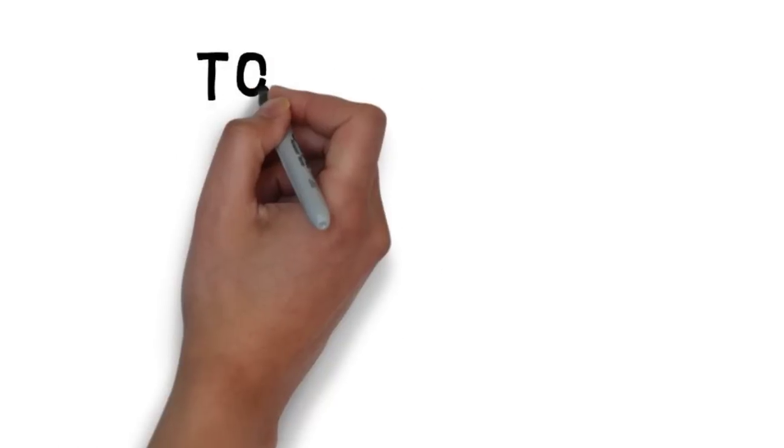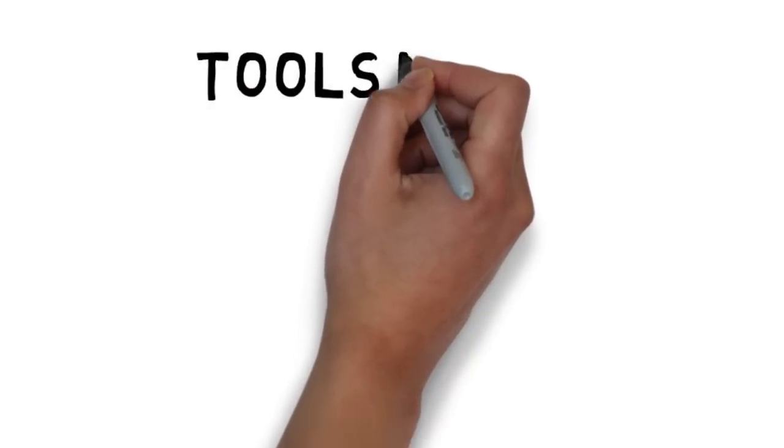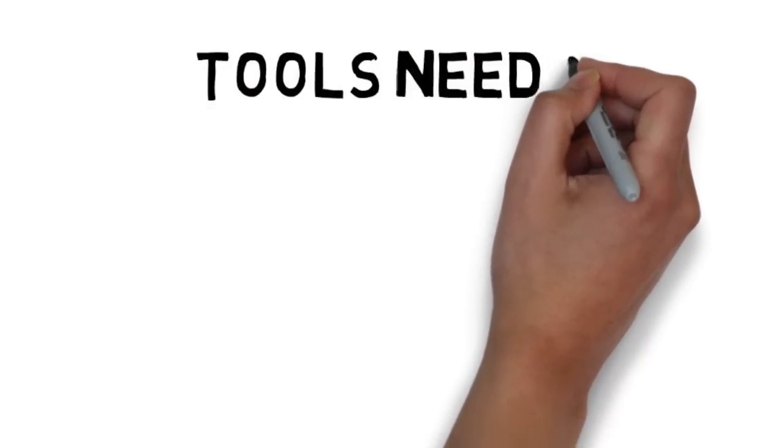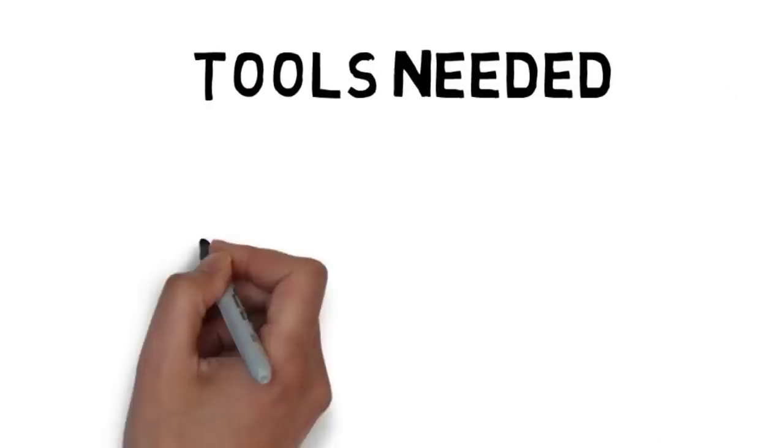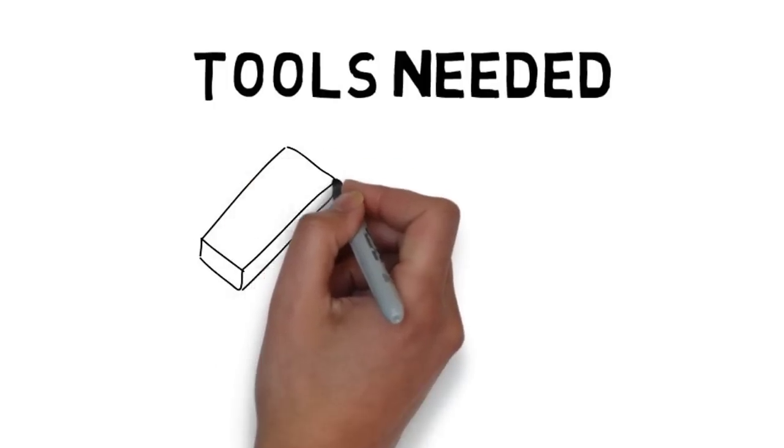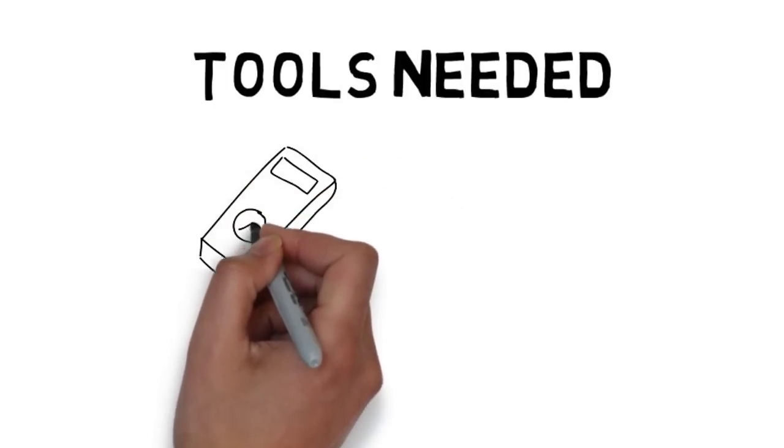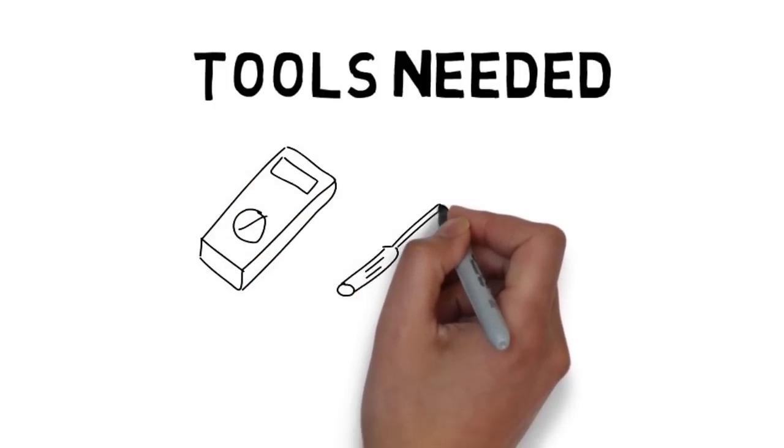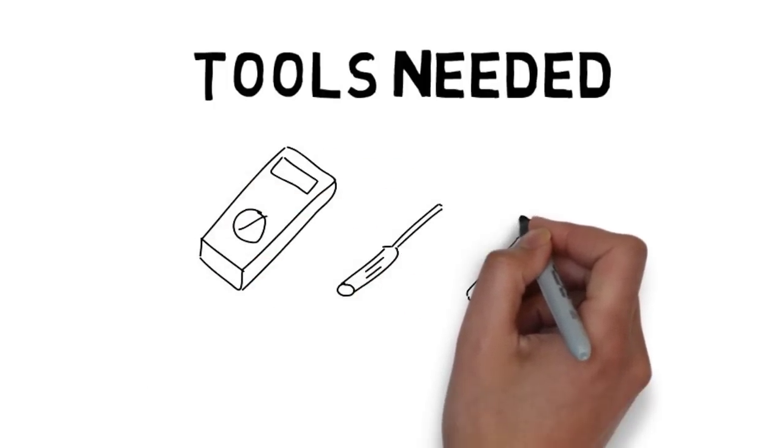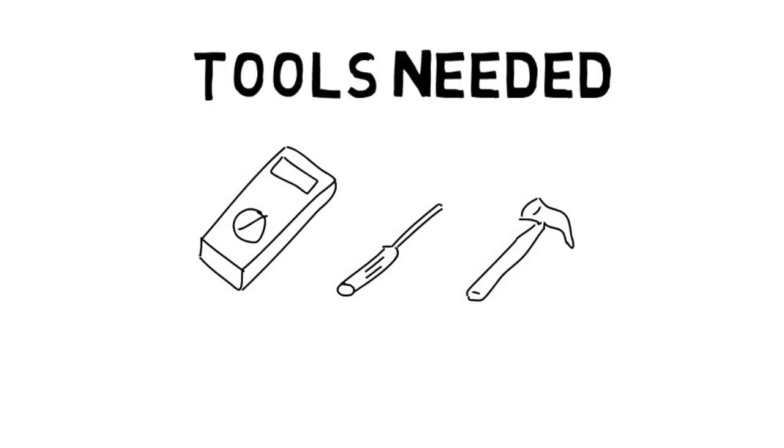You don't need any expensive tools or special tools to troubleshoot a scale system. You will need a multimeter, Phillips head and flat tip screwdriver, and a hammer. We recommend not using a test light because it really doesn't give you a good indication of exact voltage for your troubleshooting.